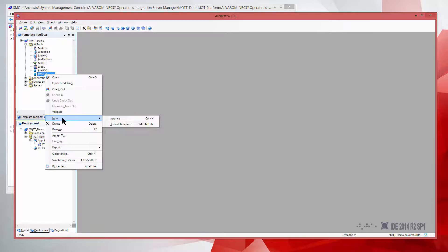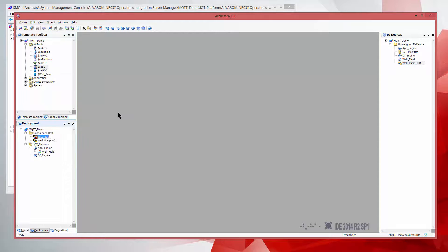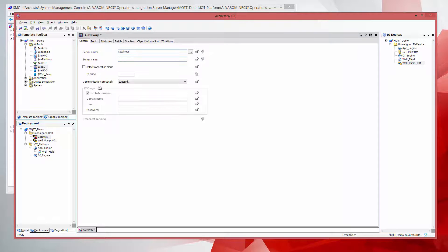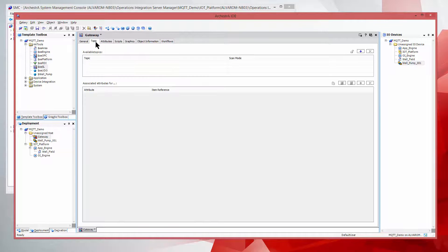Now that I have created the template, all I need to create is my instance. As I walk you through this, I'm going to show you a couple of things that people typically tend to fail when using IO Auto Assignment as part of this workflow. First and foremost, we need to create the connectivity client to the OIGateway. In this case, we're using the DDE SuiteLink client, configuring it the same as we created there, and using MQTT_G1 as the scan group as we created in the OIGateway.